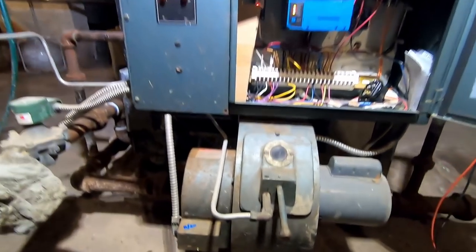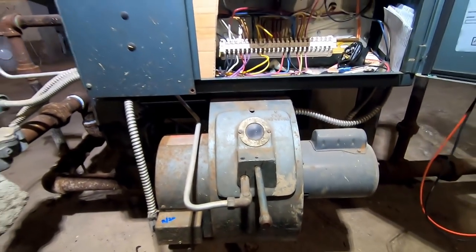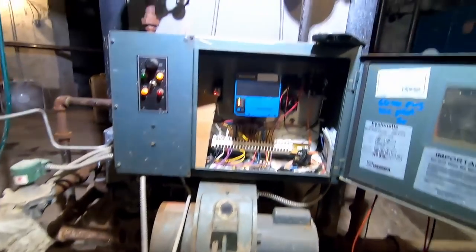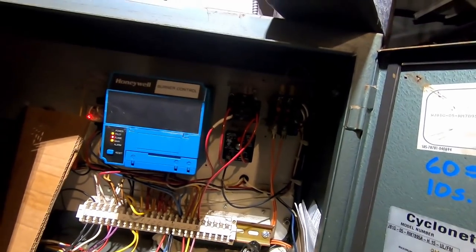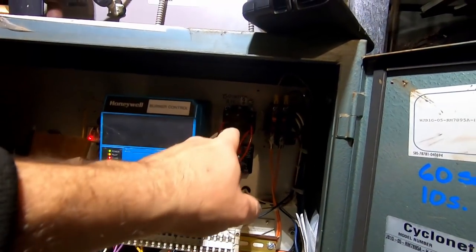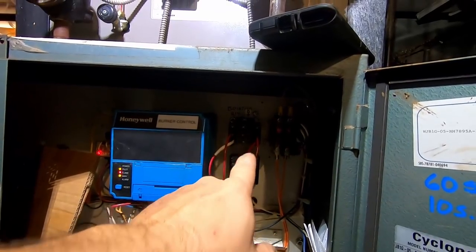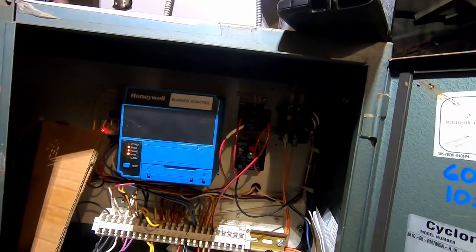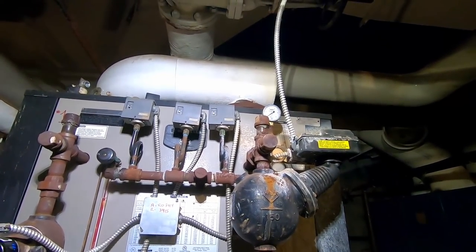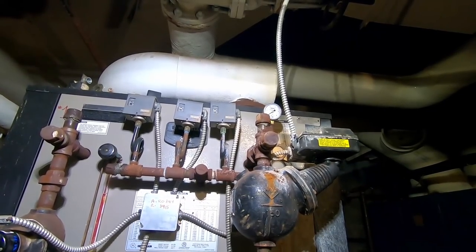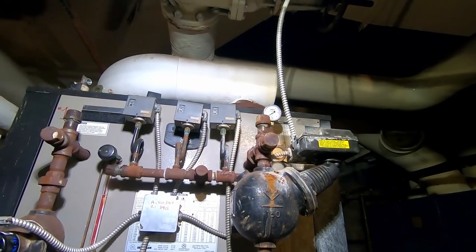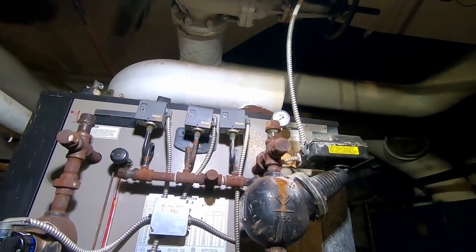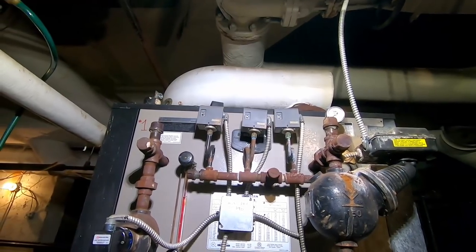So to the best of my knowledge, that's all that was really wrong with it. So we're just going to have to see, see how she acts. Now I did add a time delay to it. I put a time delay about 10 minutes on here with an isolation relay that keeps the high stage from coming on for at least 10 minutes. And then there's a switch up there, top right corner, that will shut the high stage down once the pressure builds up to around one and a half area. And the other two are just cutting cutouts.